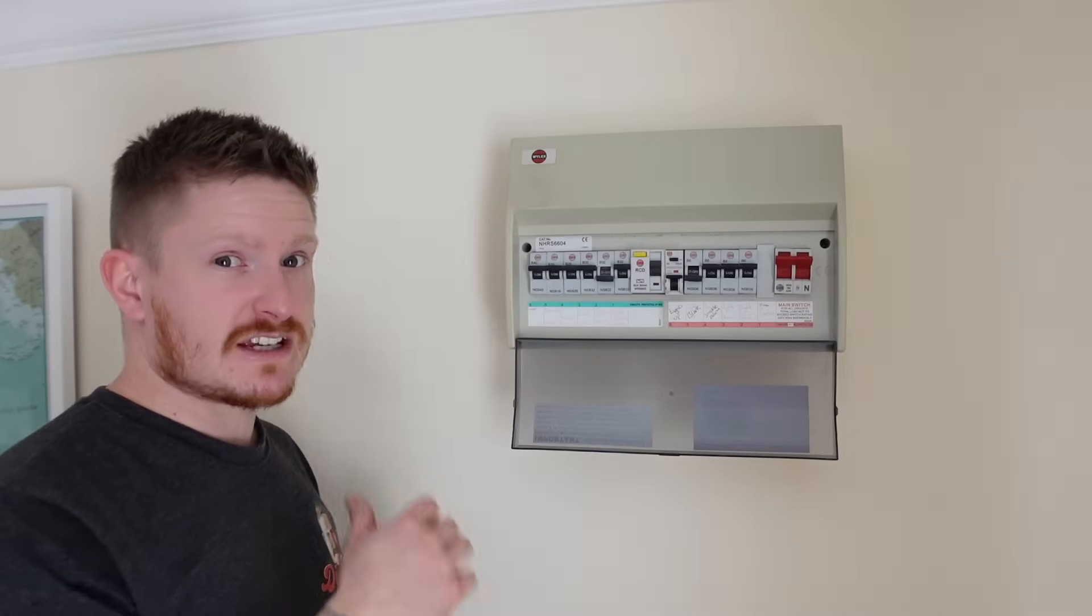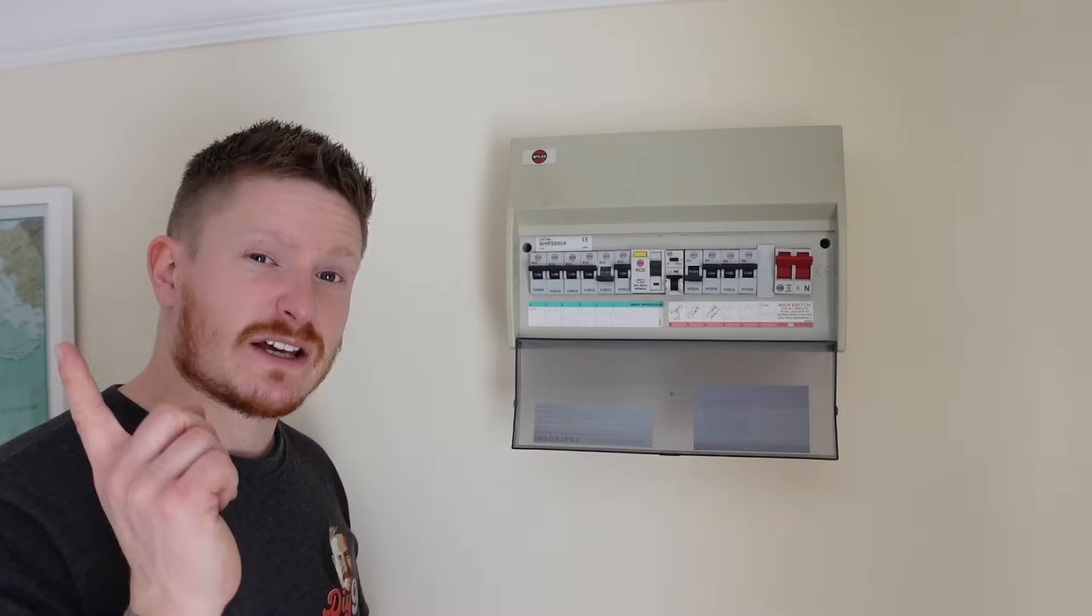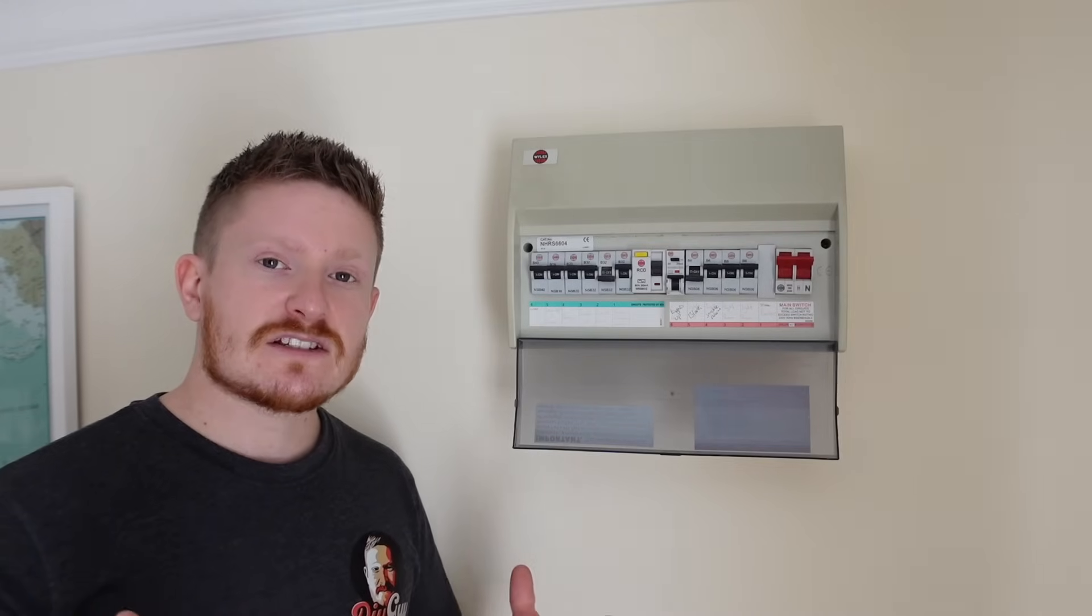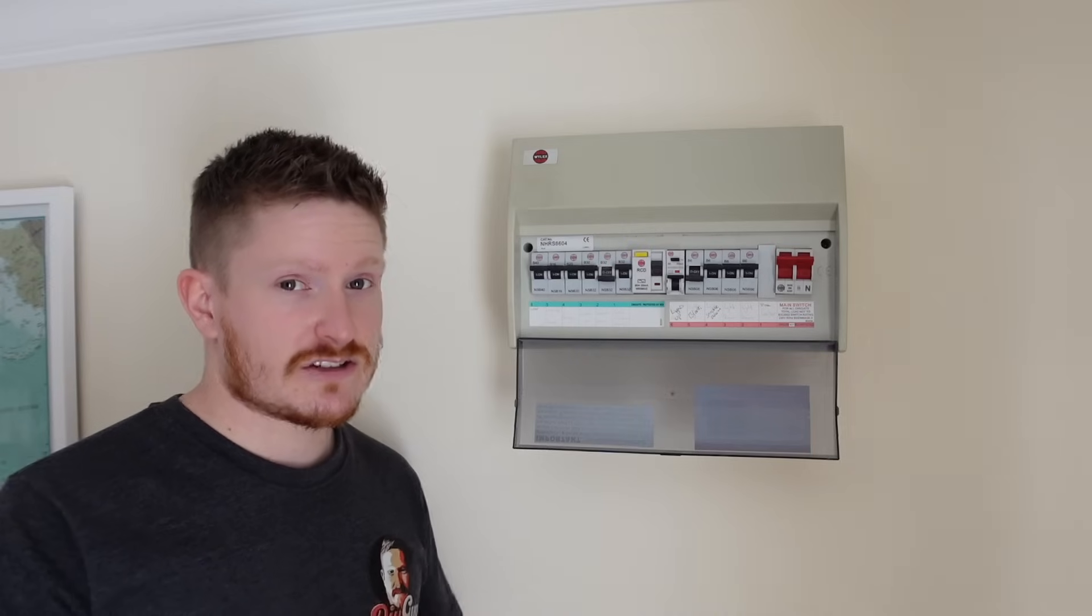If that didn't work for you and your socket tester is still sounding, you are going to need to turn off each breaker until you hear the socket tester turn off. Now to make this job as safe as we can, we need to use a lockout kit to make sure that nobody can come along and turn that circuit back on.